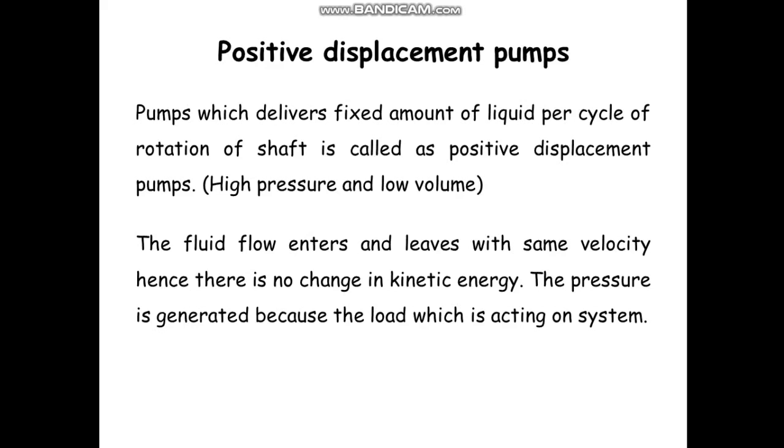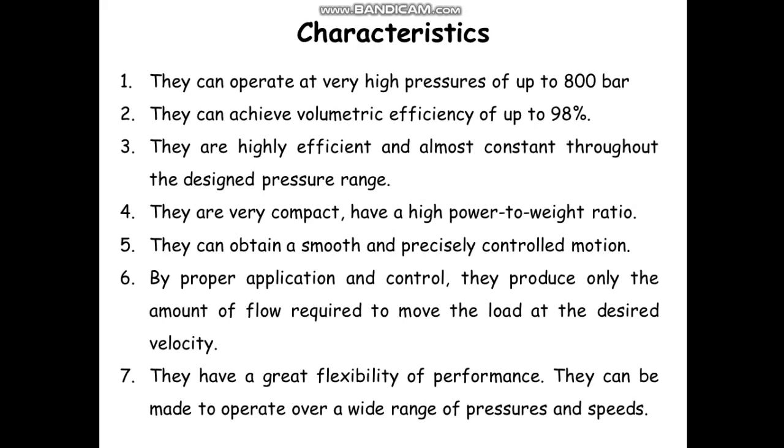So when the fluid flow enters and leaves with the same velocity, there is no change in the kinetic energy, thus the pressure is generated because of the load acting on the system. Now let us see the characteristics of positive displacement pumps. Positive displacement pumps can operate at very high pressures, up to 800 bar. They can achieve volumetric efficiency up to 98%.